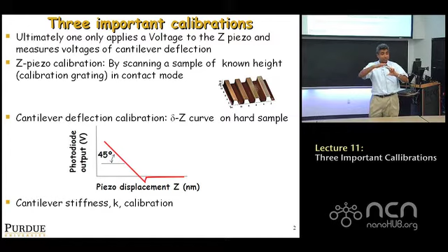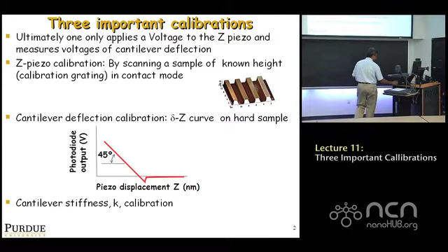So the logic is the following. I showed you that when you apply a point force, there is a linear relationship between the bending angle and the deflection. So it's okay as long as you measure the deflection, because deflection is linearly proportional to the transverse deflection also. In principle, it is linearly proportional to the amount the tip has bent up by, right? But what comes out of the photodiode is a voltage. So how do you convert that voltage into what you want to measure, which is tip deflection? How do you do that? That's the main question, and that's where we do cantilever deflection calibration. And lastly, the cantilever stiffness calibration, we'll talk about that in some more detail now. So we'll go through these three calibrations one by one.